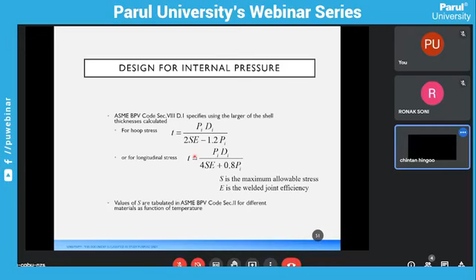Here is the maximum allowable stress versus temperature. You can see the maximum temperature of 900 degrees Fahrenheit, and here is the maximum allowable stress. At 100 degrees Fahrenheit, 12.9 ksi is your allowable stress. As your temperature gets higher, your allowable stress gets lower. So this is one case where you can use allowable stress for thickness calculations.